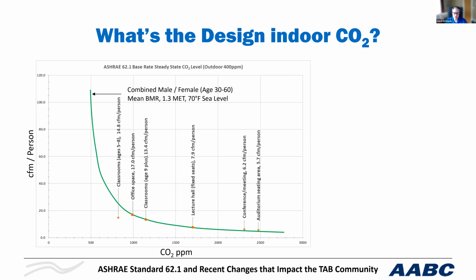And so if we take a look, what happens if we have an office where, instead of people sitting at desks, they're all walking around all the time? They have a higher metabolic rate, they're generating more CO2, so the curve shifts up. And you need a lot more ventilation to maintain that same 1,000 parts per million, or just maintain any of those dots along that curve. So if you look at the office value again, originally it was 17 CFM per person, but with people walking around, it's now about 25 CFM per person that you need.